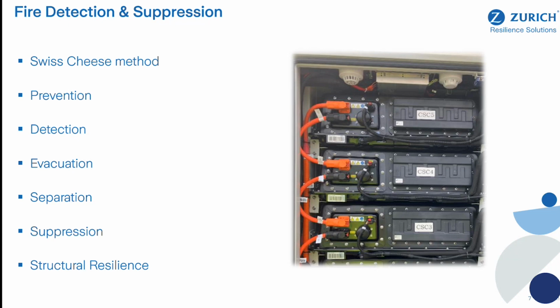A lithium-ion battery that is getting very hot, but not quite at thermal runaway temperature levels, about 20 degrees before that, will start emitting some hydrogen gases or flammable gases. So the off-gas detector will actually spot those gases, hopefully 20 degrees or so before the battery does get violent, and we can isolate the system there, cool it down as quickly as we can, and we've obviously avoided a nasty situation. So off-gas detection is a very useful form of nipping things in the bud.